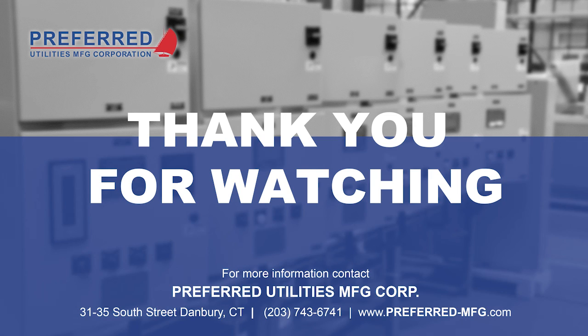What is a good cycle runtime for fuel pumps? There is such a huge range of day tanks and belly tank sizes now that there's just a huge range in cycle times. I like to be able to top off a tank from 50 to 80% in less than an hour. So I'll take the day tank or the belly tank volume, multiply by 0.3, the difference between 80% and 50%, and then divide by my gallons per hour, and hopefully come up with a number that's less than 60 minutes.